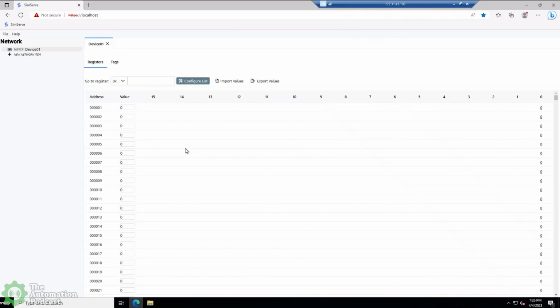All right. Next up, what we can do is just open this device up here. And basically what you're seeing is all the memory registers in the device. By default, it starts out with every possible Modbus register. However, you can configure it to narrow that list down if you want it to match a device exactly. And so on this table here, we're looking at the 0x registers, or the coils, however you know them, but there's a few different nomenclatures out there. And what we can do here, I'm just going to click on a bit here to toggle. What I just did was I just turned the 0x register 1 on.